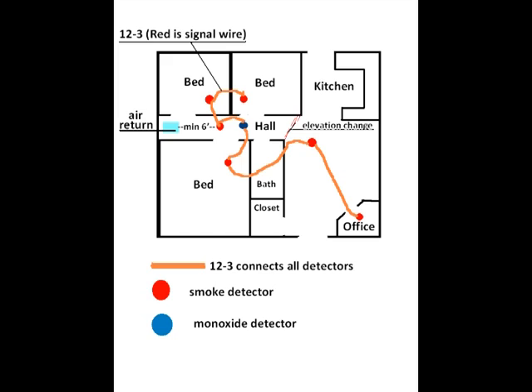If you look at the diagram, you see that there's a smoke detector in every bedroom. There's a smoke detector in the hallway. The little blue dot is a carbon monoxide detector, which is a new code. There's also a smoke detector in the office, which is new code. Smoke detectors are not required in bathrooms or closets. The red wire in the 12-3 acts as the signal wire that connects all the smoke detectors and carbon monoxide detectors together so that if one goes off, they all go off.